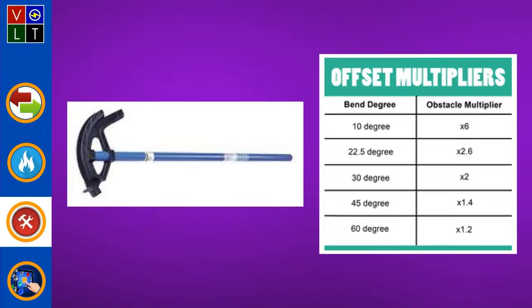That's a job spec. That's not the code. The code says no more than 4 quarter bends per wiring method, between pull points. A pull point is not necessarily a 1900 box, as Mike mentions, but what we're doing is going pull point to pull point. If you put in more than 360 degrees, that's going to make your wire really hard to pull. I know a lot of guys tell me, 'Willie, we could go 420 degrees all day.' And I'm like, dude, if you go 420 degrees on a pipe run, it's going to make it really hard to pull. So try not to do that. I don't think an inspector will ever really bust you for that, but I would not. I always say you pipe it, you pull it.